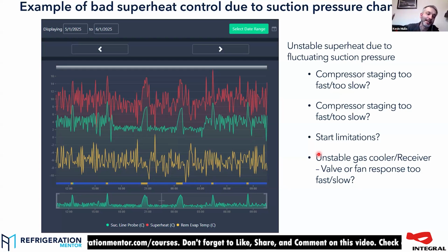And what happens if you go too high is that the gas cooler side of the controller is like, well, I need to keep the gas cooler pressure up. So it'll just shut the high pressure valve, and you'll end up backing up a ton of CO₂ into the gas cooler, especially if you've got a massive gas cooler. And then all of a sudden you have no space whatsoever left. It panics because the head pressure has gone through the roof.